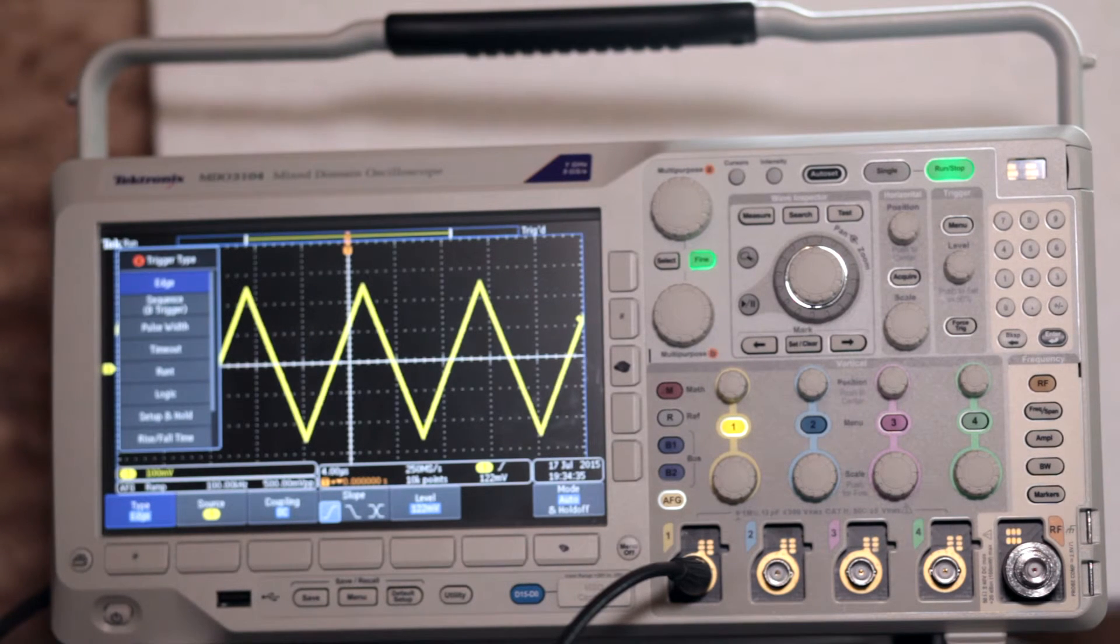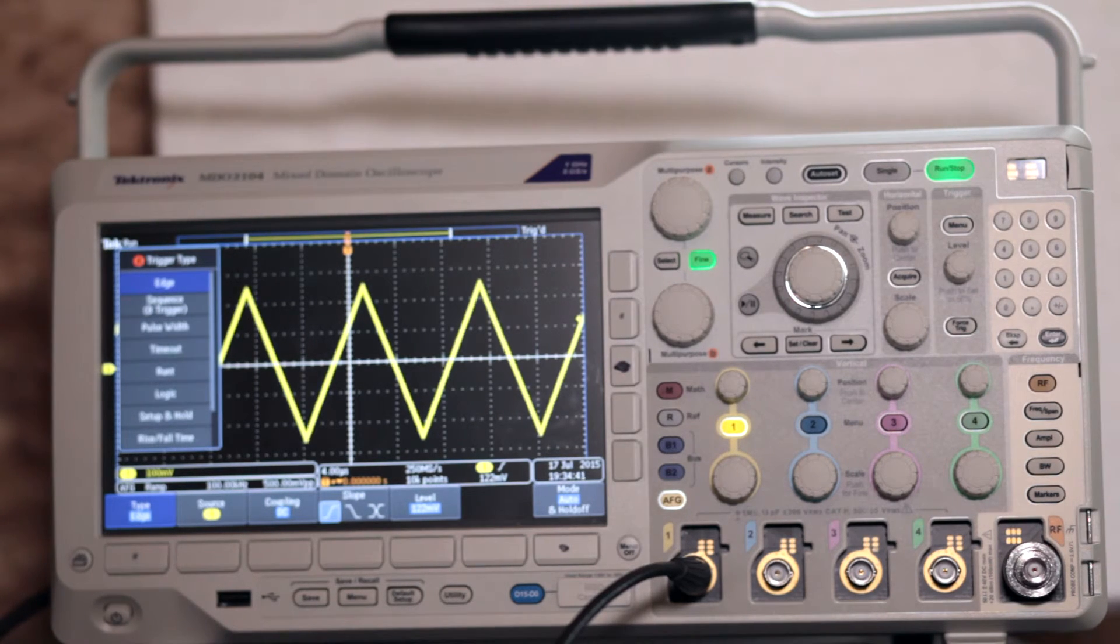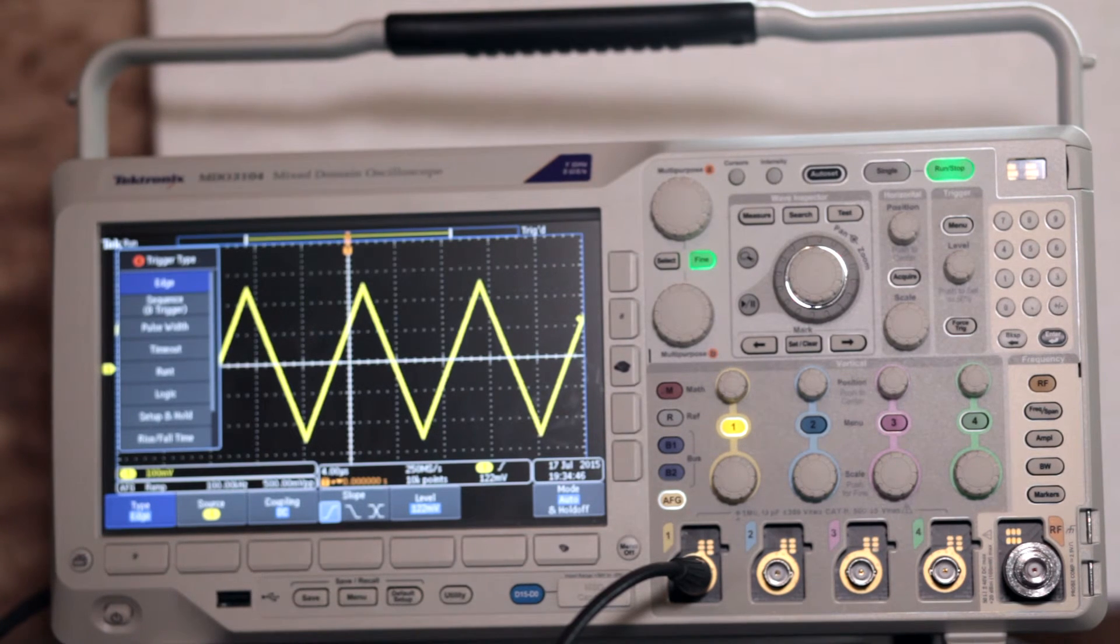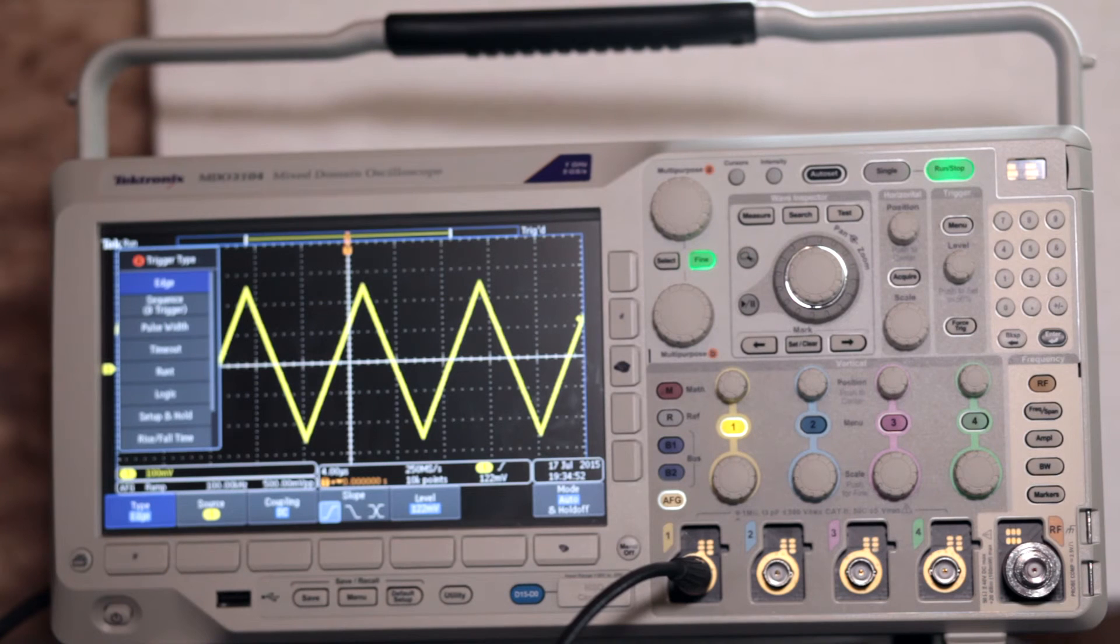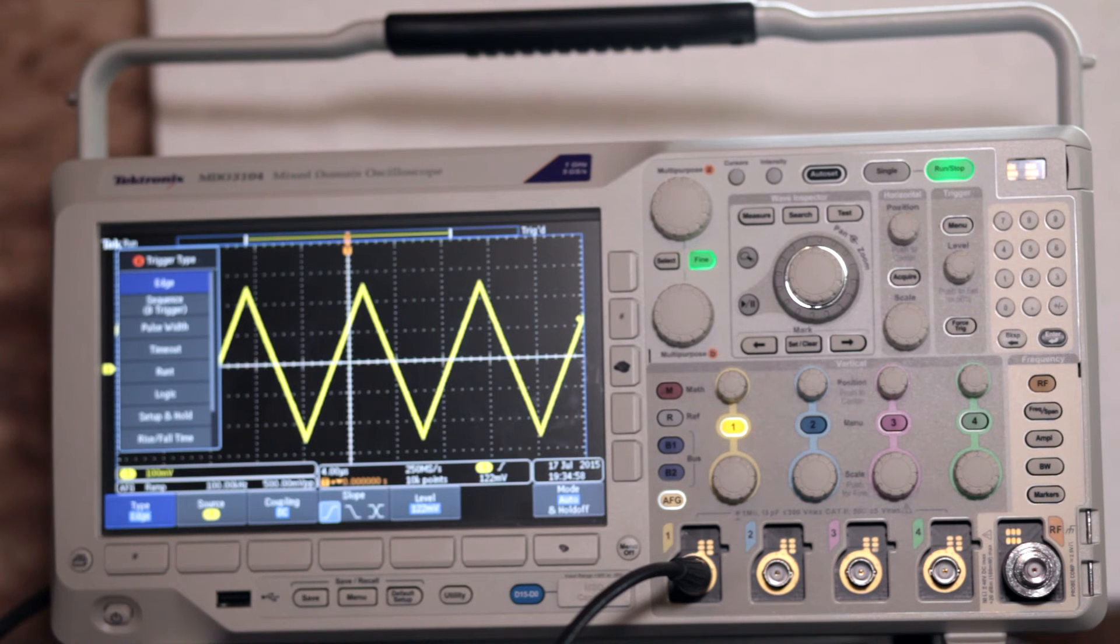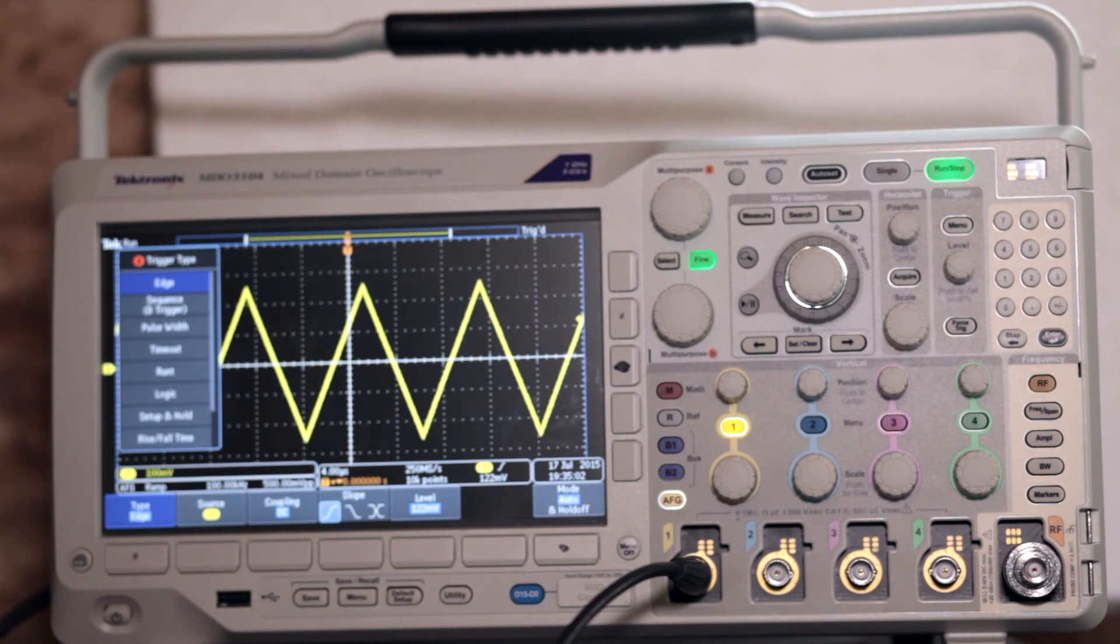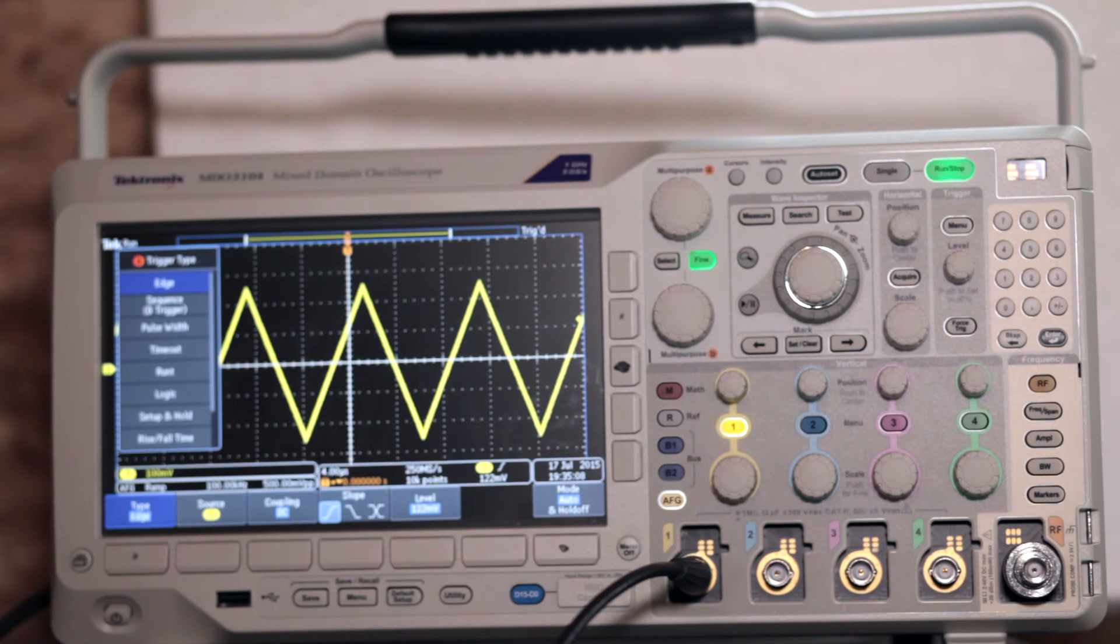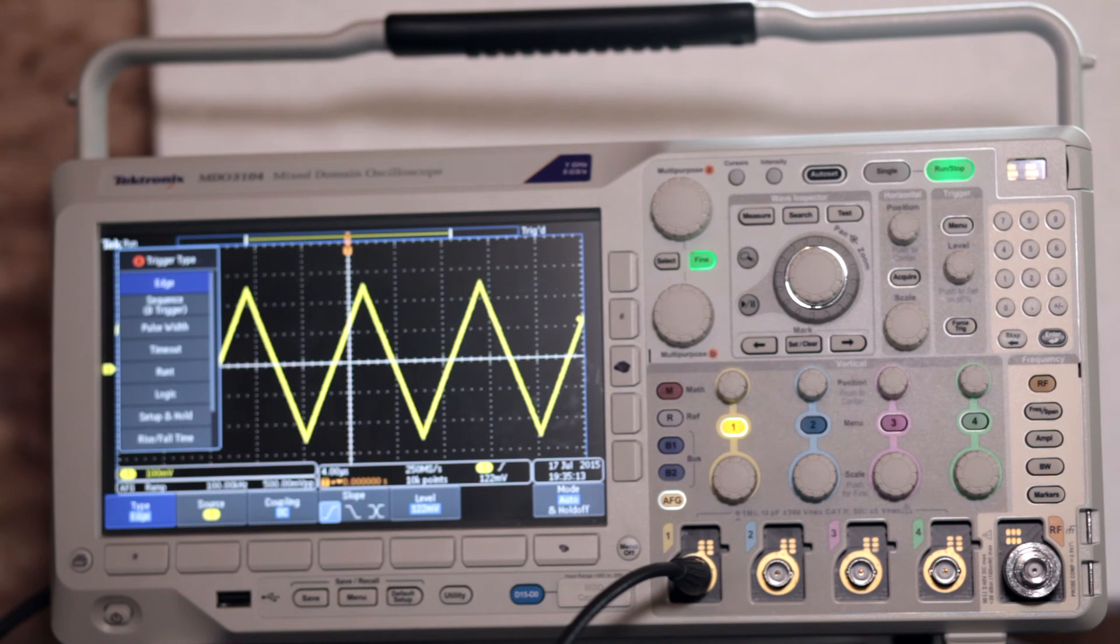The sequence trigger type permits the operator to continue a main event with a delayed event to display a complex signal. Pulse width triggering, in conjunction with digital signals, permits the operator to trigger on pulses less than, greater than, equal to, or not equal to a time interval that you can specify. Timeout triggers when the signal remains above or below a specified value for a specified amount of time. Runt triggers on a signal that crosses one level but does not cross another level before passing back through the initial threshold.